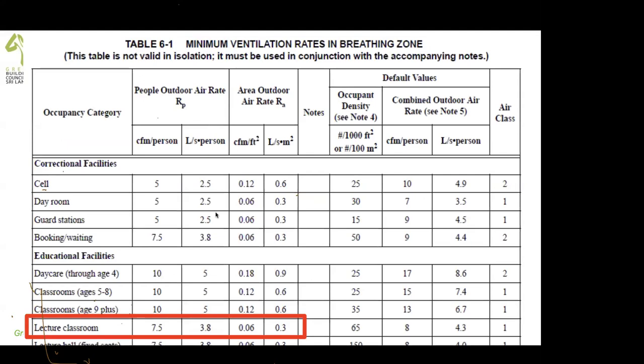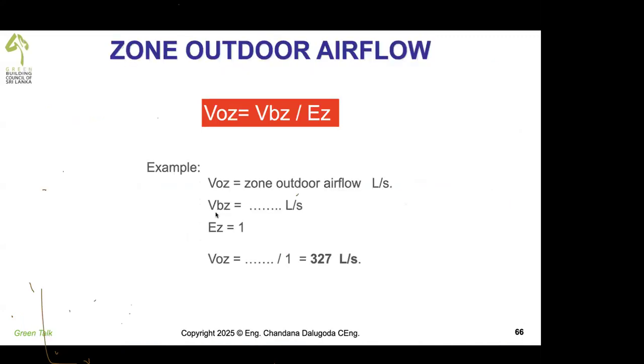I have given example, lecture room. People outdoor air rate is 3.8 liters per second per person. Let us multiply by number of people. Outdoor air rate, area rate, 0.3 liters per second per square meter multiplied by the area. So you get, and then divide by effectiveness. Of course, effectiveness is 1 for our systems, supply air and return air positively.